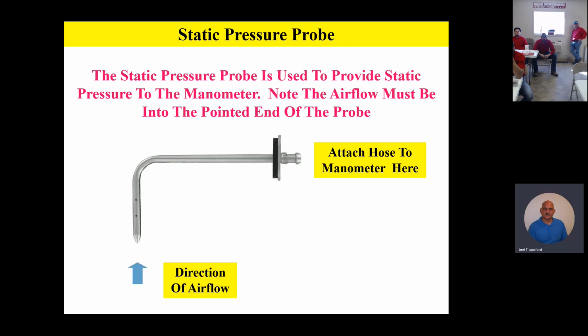Now you're going to notice the airflow has to be pointed into the pointy end of the probe. So always make sure that the pointy end of the probe is into the direction of the airflow, and then you attach the hose to the little hose barb on the back of the static pressure probe. And these static pressure probes, by the way, come in all different sizes and lengths, I should say.